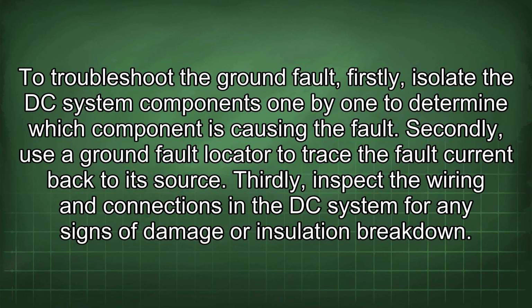To troubleshoot the ground fault, firstly, isolate the DC system components one by one to determine which component is causing the fault. Secondly, use a ground fault locator to trace the fault current back to its source. Thirdly, inspect the wiring and connections in the DC system for any signs of damage or insulation breakdown.